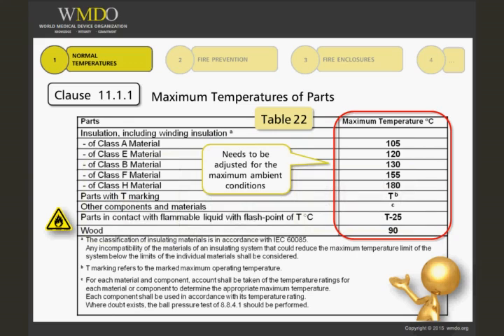These maximum temperatures have to be adjusted for the maximum equipment ambient conditions specified by the manufacturer. So if we are running a test at 25 degrees Celsius and they have a maximum operating ambient of 40 degrees Celsius, then we would have to add 15 degrees Celsius to all of the measured temperatures to get to the maximum temperature to compare with the limits in the standard.